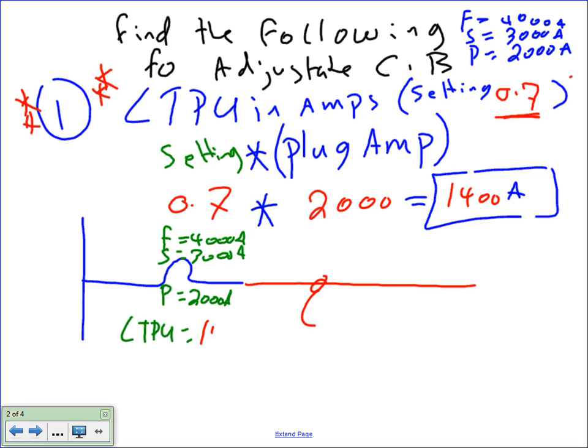You're going to use the 1,400. When you go to any of your projects, they call the long time pickup the trip size. They call it the trip size. So the long time pickup, or the trip size, is what we size the cable based on. Very, very important. Okay, so the first thing, you need to find the amp size for the long time pickup, or the trip size.